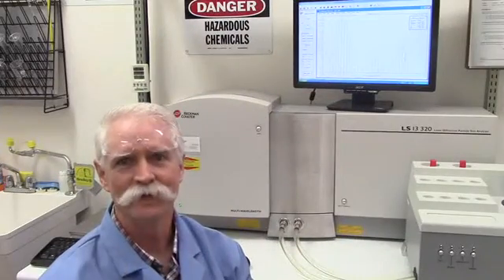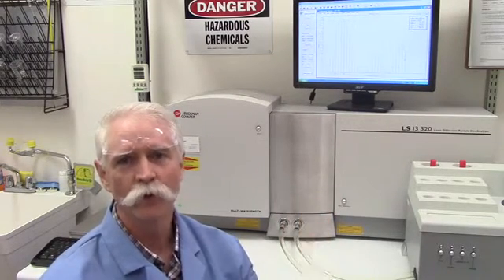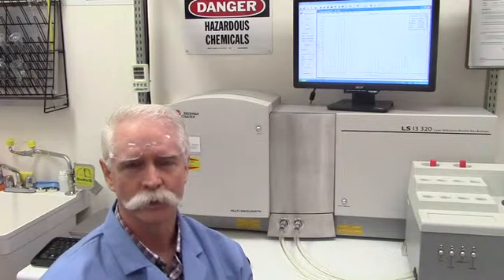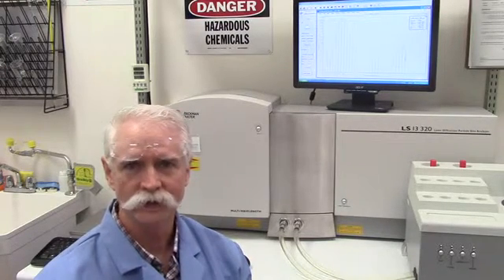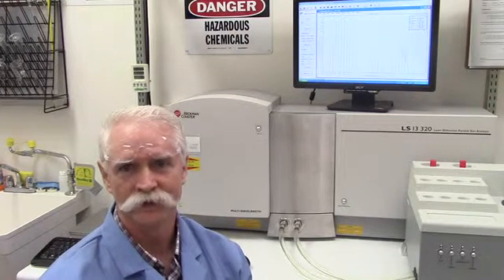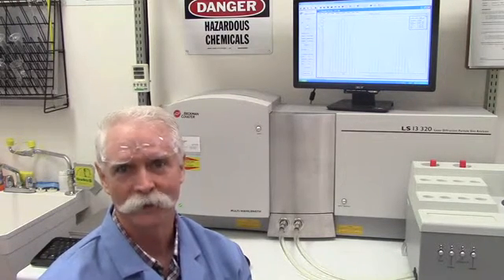Probably the premier feature in the LS13320 system is its accuracy. It's got over 140 detectors that allow the customer, when they analyze a sample, to be able to resolve peaks that are close together, but also you can rely upon the answer that the instrument is giving you to be both repeatable and accurate.